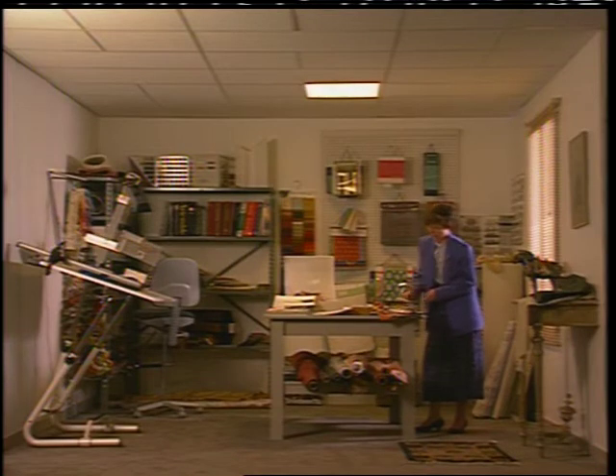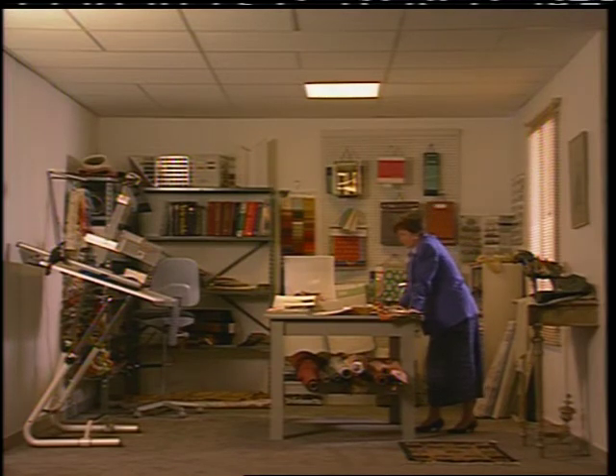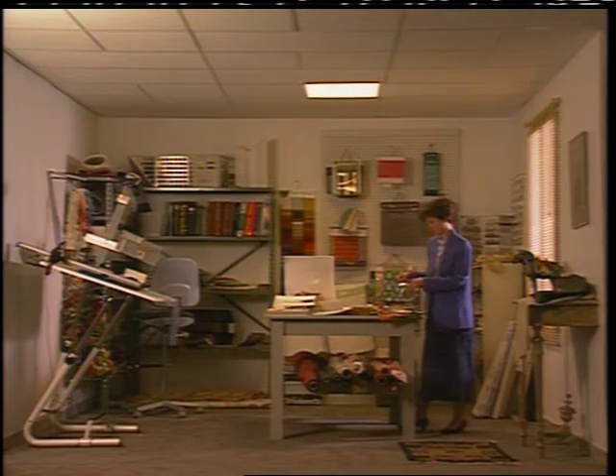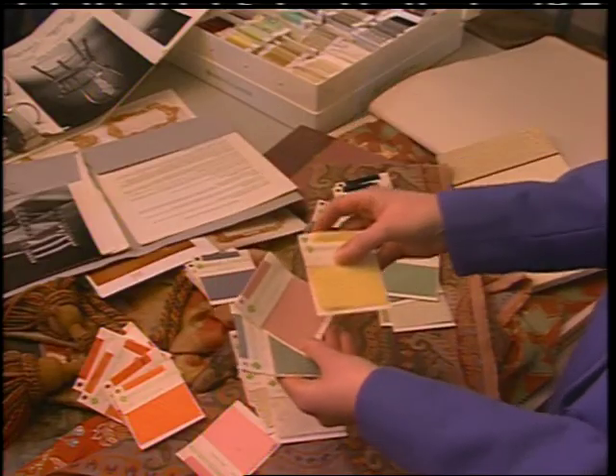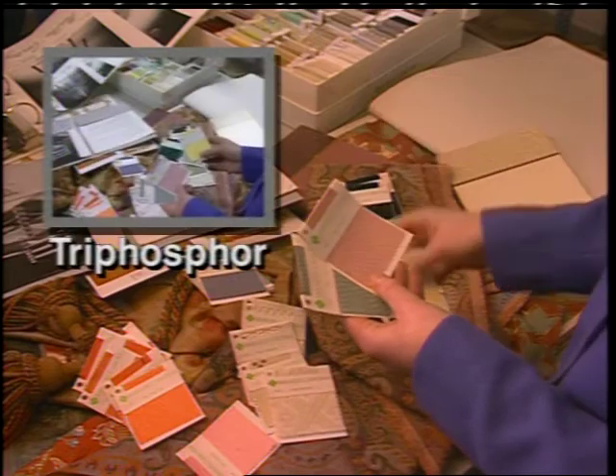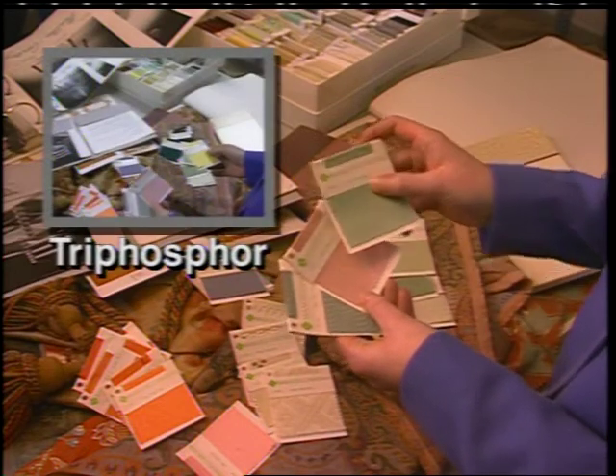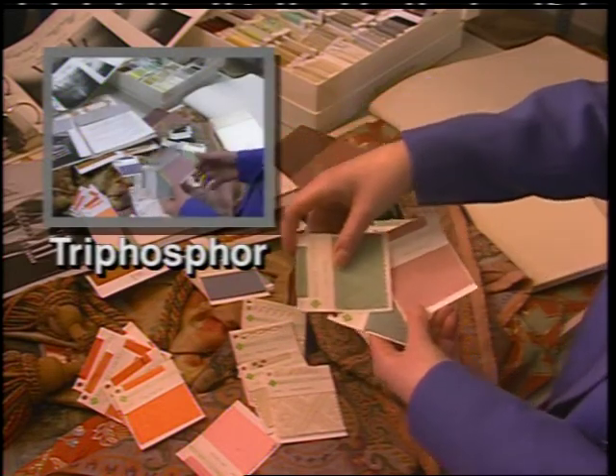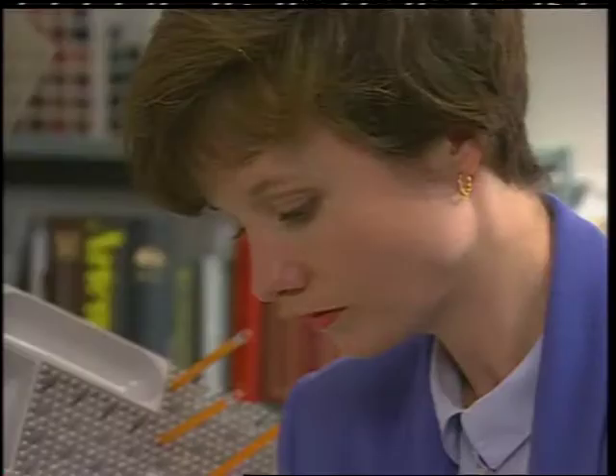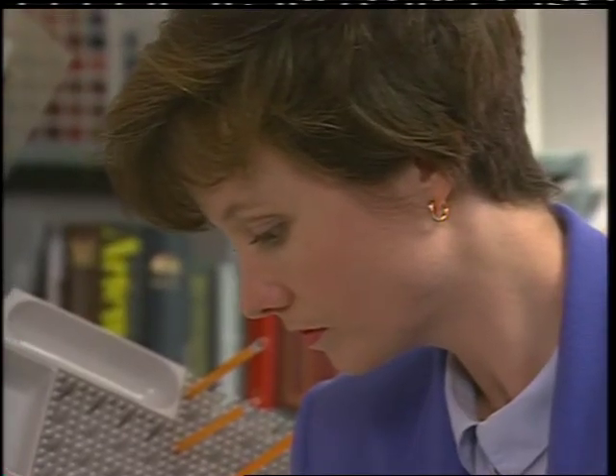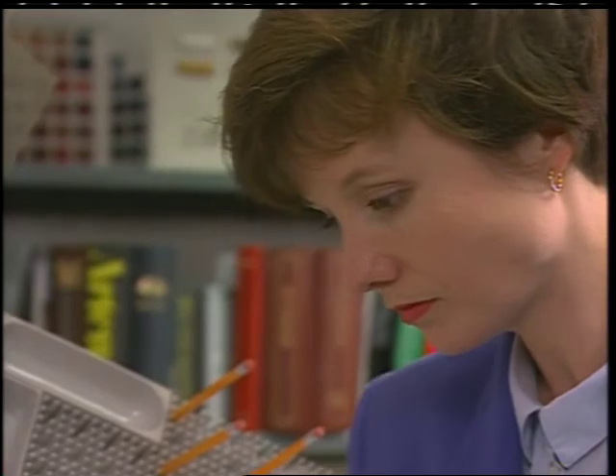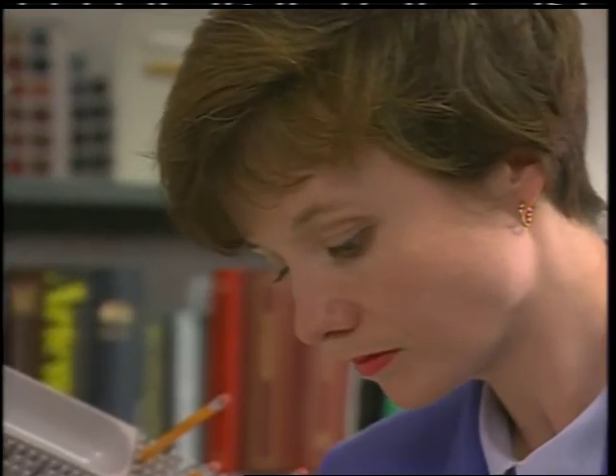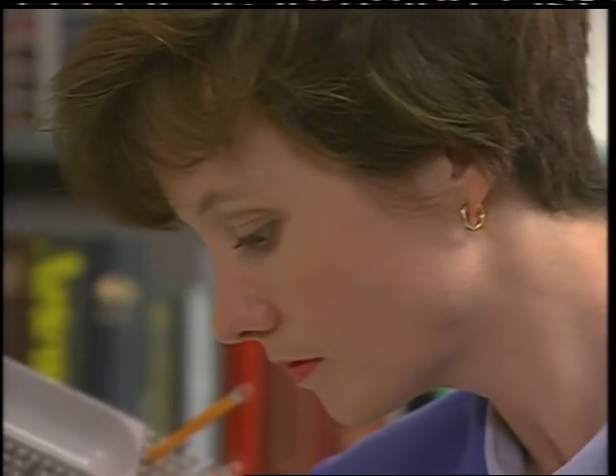High-intensity discharge, or HID lamps, such as compact metal halide sources, produce from 60 to 80 lumens per watt. These lamps are a good choice for certain tasks. The problem with most HIDs for a design studio is color. As always, the light must be matched to the task. The studio illustrates how the relative importance of color rendering in a lighting environment affects decisions about energy efficiency.